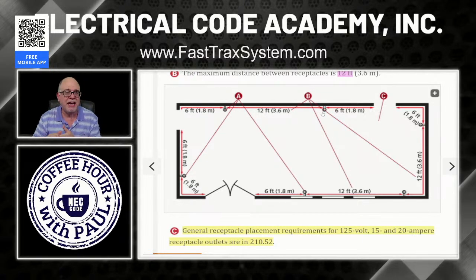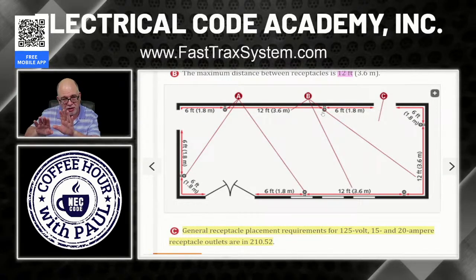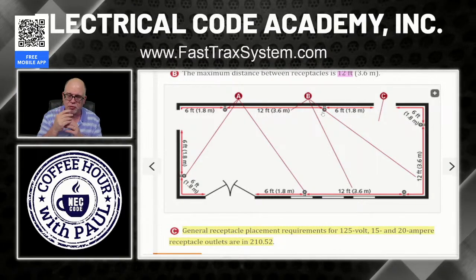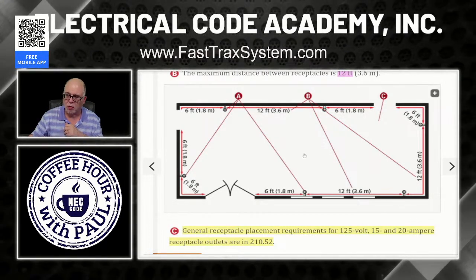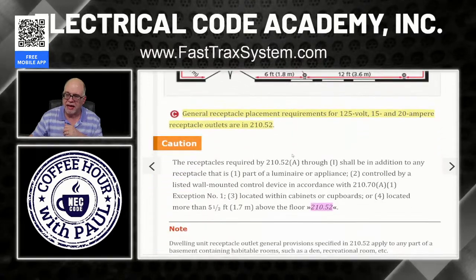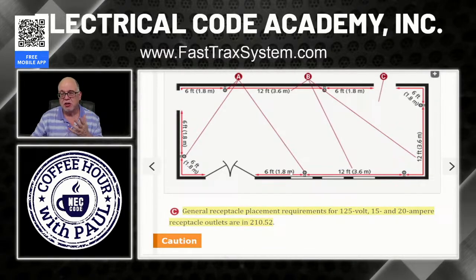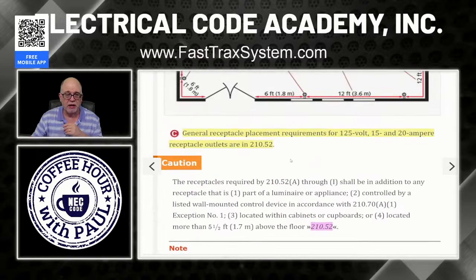Now, that doesn't mean that we have to put a switch to meet the placement requirement that we show in this illustration and add another receptacle and switch it. No, we could simply take a duplex receptacle. Remember, that's two receptacles. Break the tab on the hot side and the top one is switched and the bottom one is hot all the time. So the one that's hot all the time meets the requirements of 210.52A, no problem. The one that's switched is being switched in lieu of a lighting outlet in that room, and that is permitted by 210.70A1, exception number one.